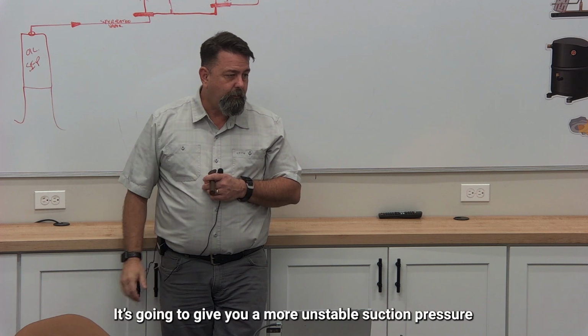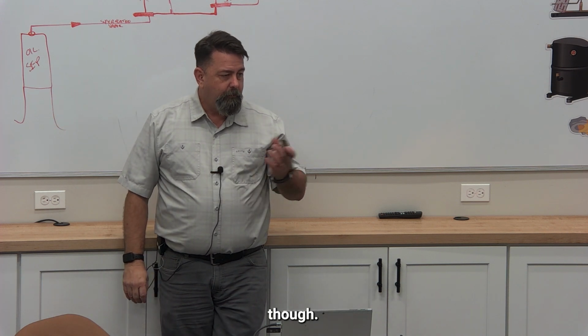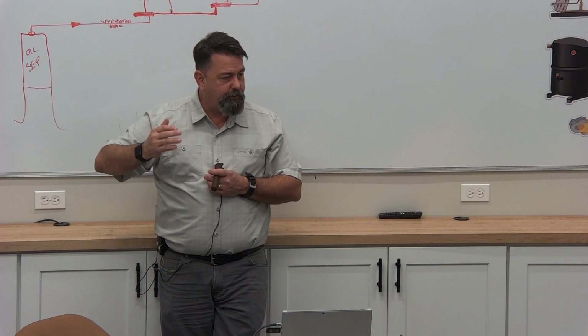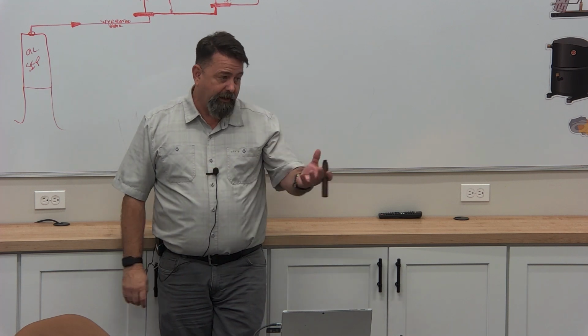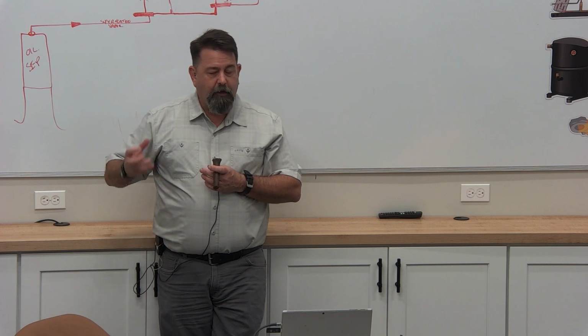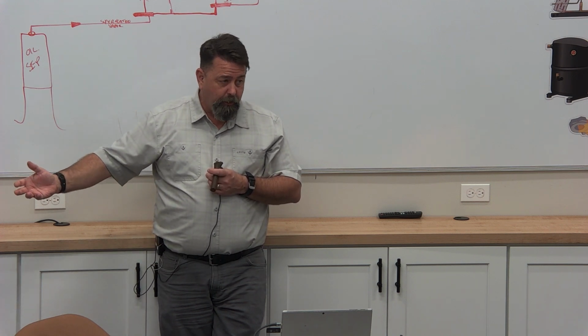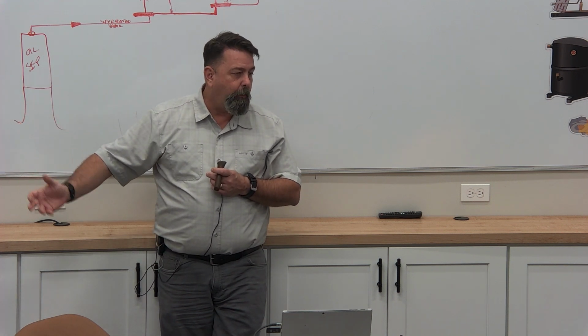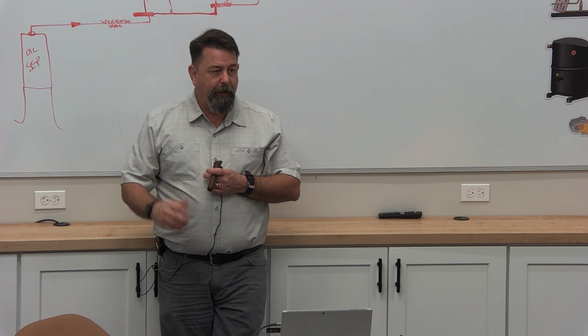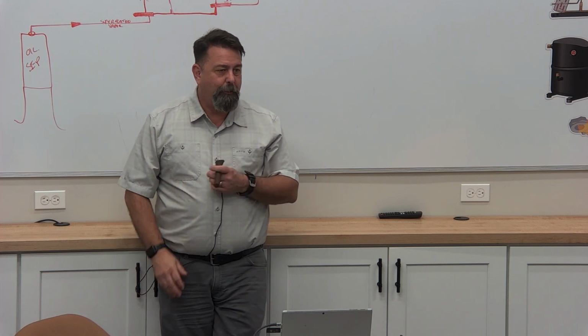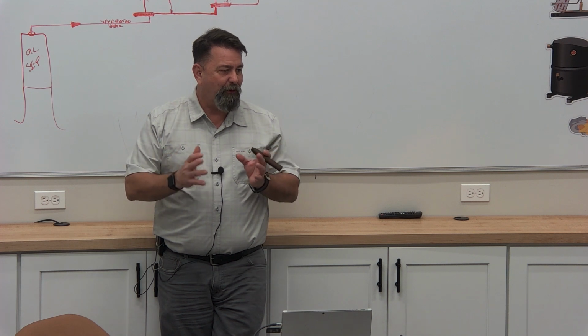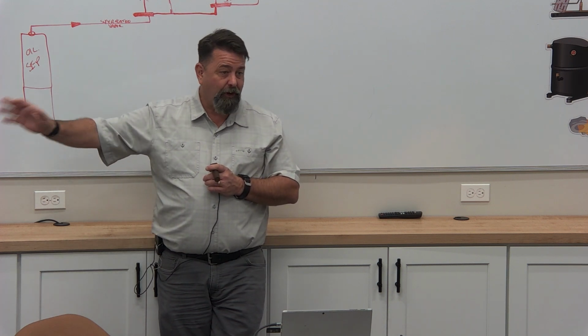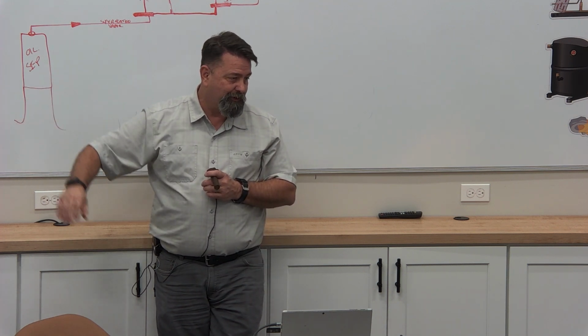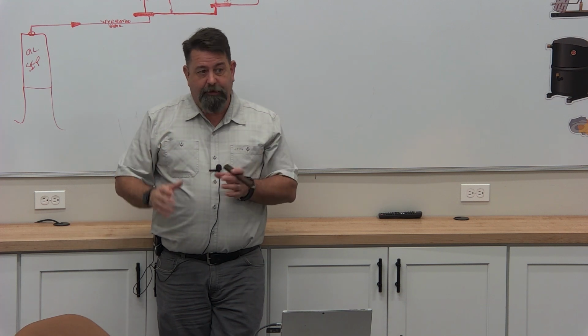But it's going to give you more unstable suction pressure. That's exactly what it's going to do. If I'm controlling my compressors with digital unloaders, I can handle that, it's not a problem. But if I've got my compound cooling rack down to two compressors because my rack keeps getting smaller with more efficient cases and covers on my glass doors, that's not so great.